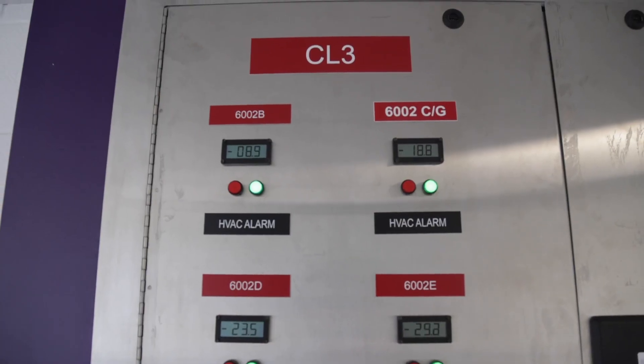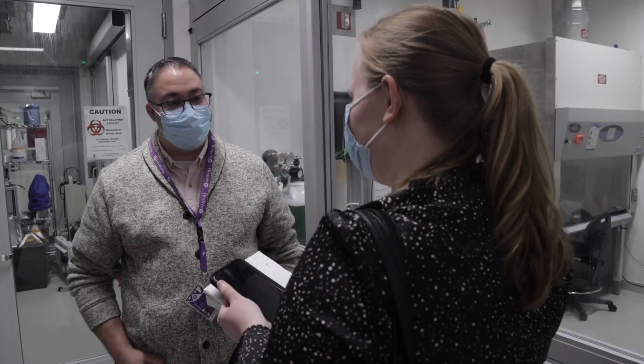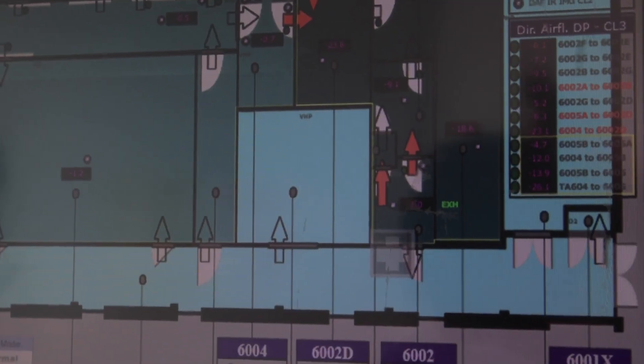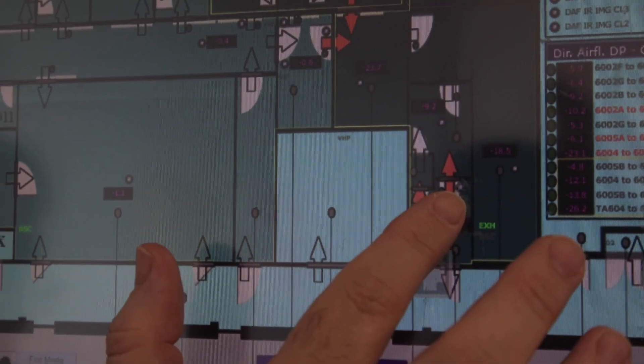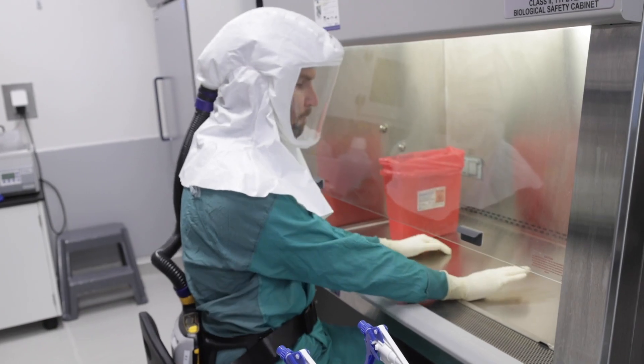If this is the doorway, we would call the lab side dirty air and the other side clean air. If a user were to open the doorway, the lab automatically adjusts and pulls air into the dirty lab, preventing the dirty air from the laboratory flowing out into the clean portion of the room — and that happens every single time a user opens or closes the door.